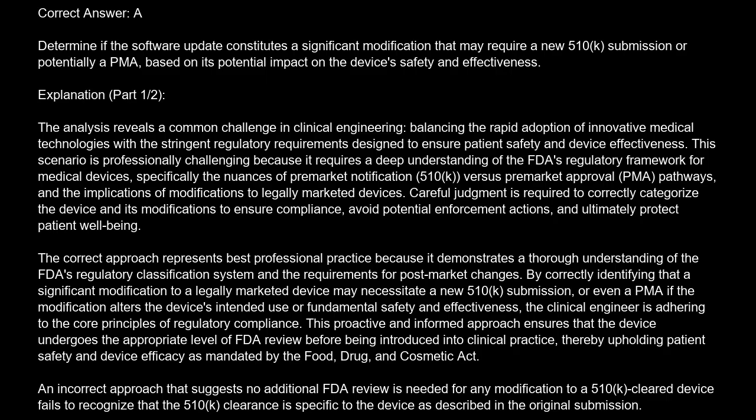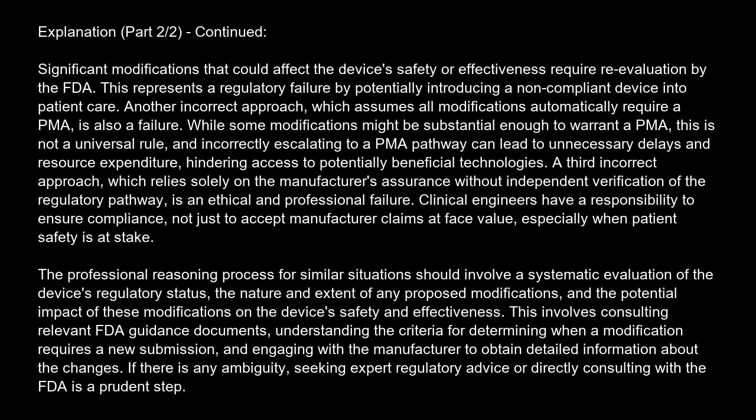An incorrect approach that suggests no additional FDA review is needed for any modification to a 510K cleared device fails to recognize that the 510K clearance is specific to the device as described in the original submission. Significant modifications that could affect the device's safety or effectiveness require reevaluation by the FDA. This represents a regulatory failure by potentially introducing a non-compliant device into patient care.